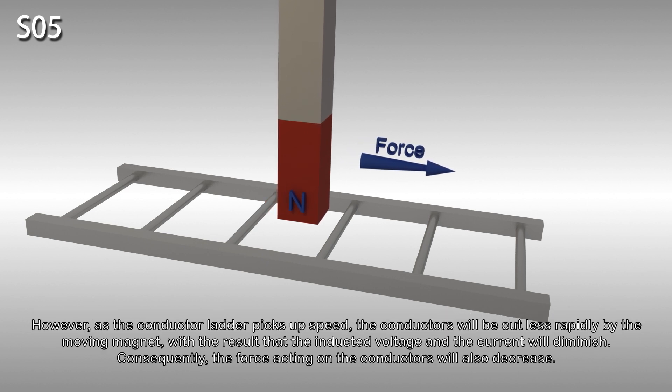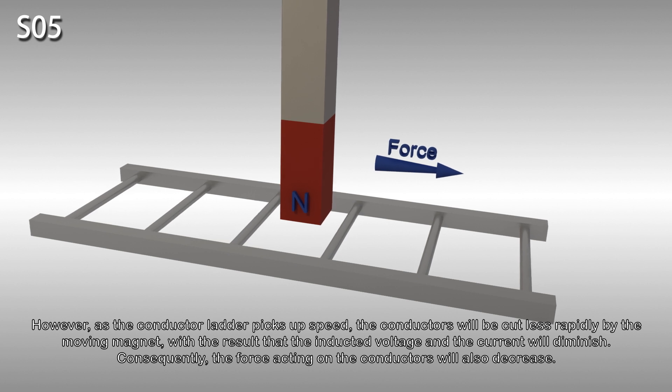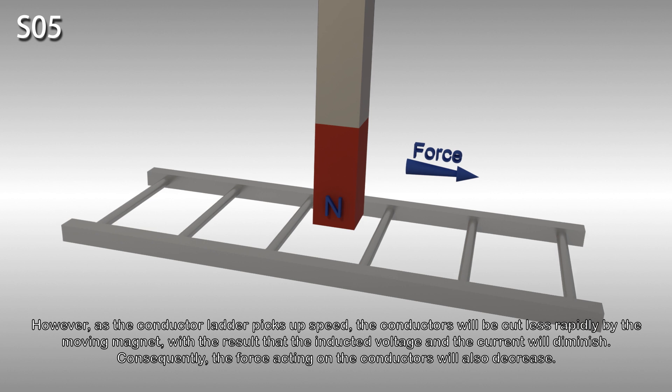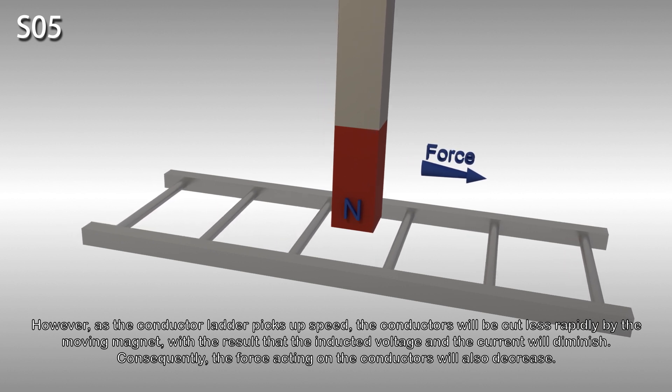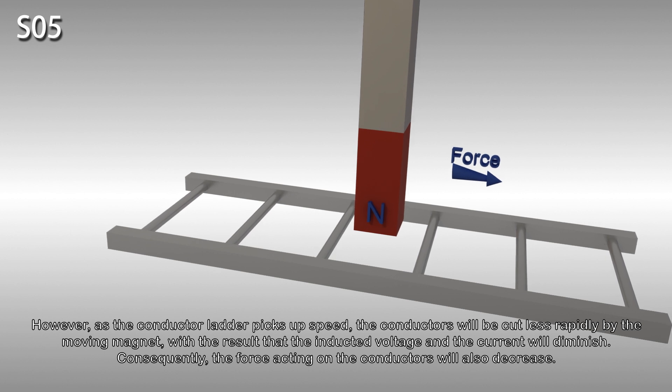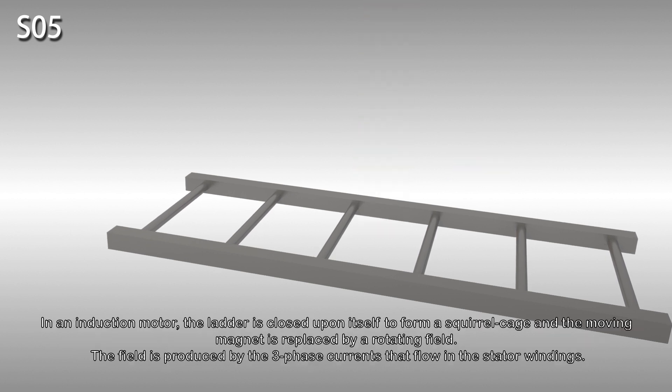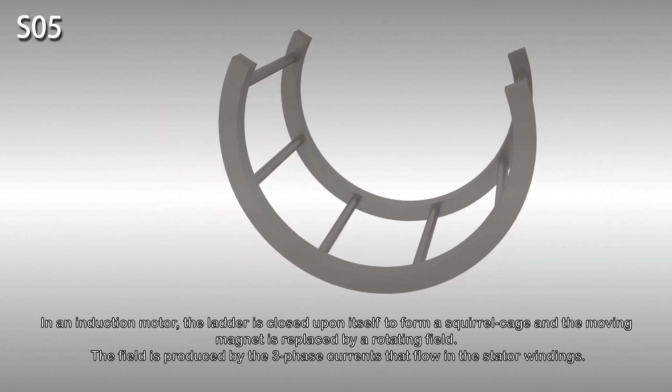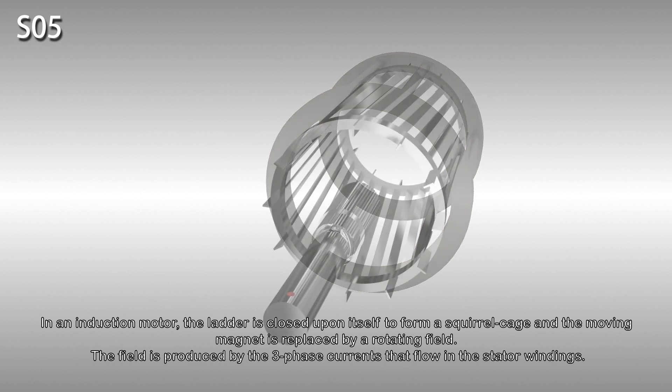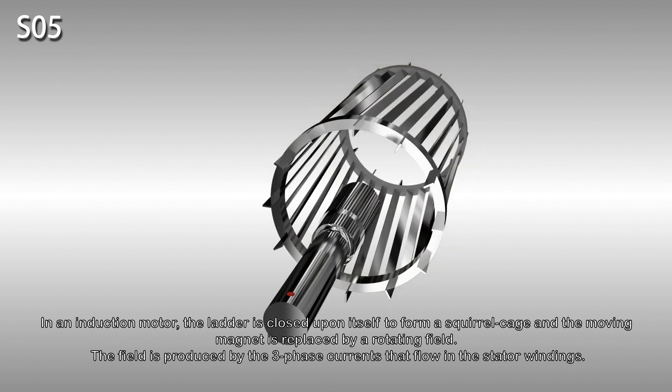However, as the conductor ladder picks up speed, the conductors will be cut less rapidly by the moving magnet, with the result that the induced voltage and the current will diminish. Consequently, the force acting on the conductors will also decrease. In an induction motor, the ladder is curved to form a squirrel cage and the moving magnet is replaced by a rotating field. The field is produced by the three-phase currents that flow in the stator windings.